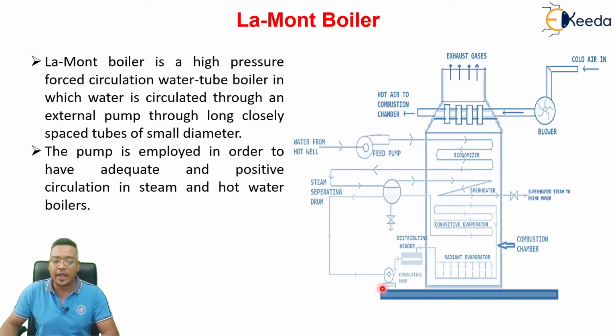I have already told that when the water is coming from the boiler drum through the downcomer and that water is going into the evaporator, if a pump is used in between these lines or between this path, then this will be a forced circulation. If a pump is not used, then it will be a natural circulation. So the Lamont boiler is a forced circulation boiler because we are using a pump. You see, this is the downcomer and through this downcomer water is coming and it is going into the radiant evaporator. So this is a forced circulation boiler.